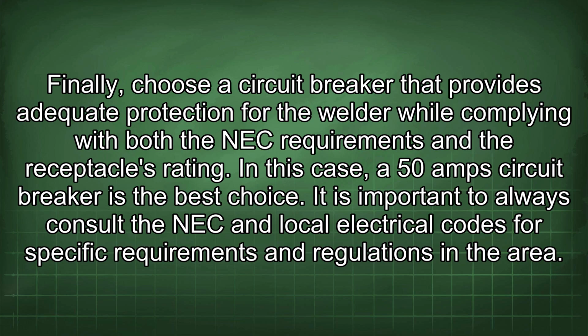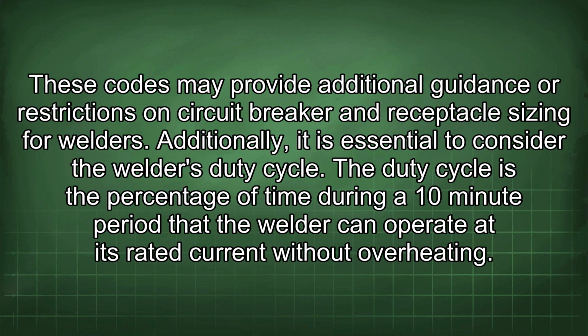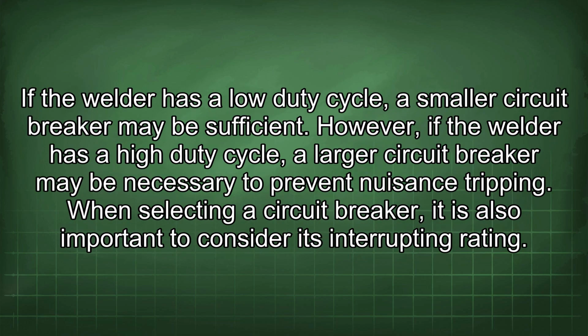It is important to always consult the NEC and local electrical codes for specific requirements and regulations in the area. These codes may provide additional guidance or restrictions on circuit breaker and receptacle sizing for welders. Additionally, it is essential to consider the welder's duty cycle. The duty cycle is the percentage of time during a 10-minute period that the welder can operate at its rated current without overheating. If the welder has a low duty cycle, a smaller circuit breaker may be sufficient. However, if the welder has a high duty cycle, a larger circuit breaker may be necessary to prevent nuisance tripping.